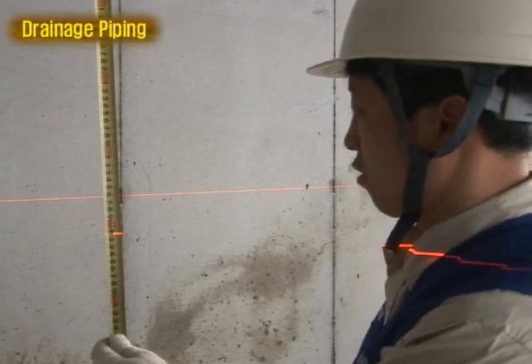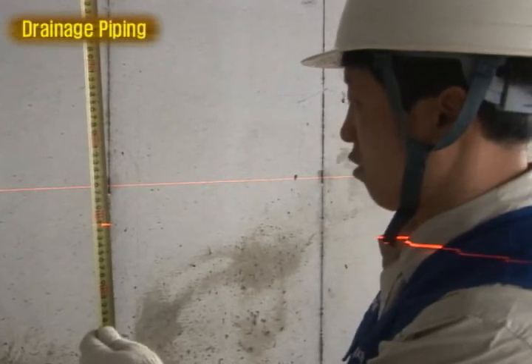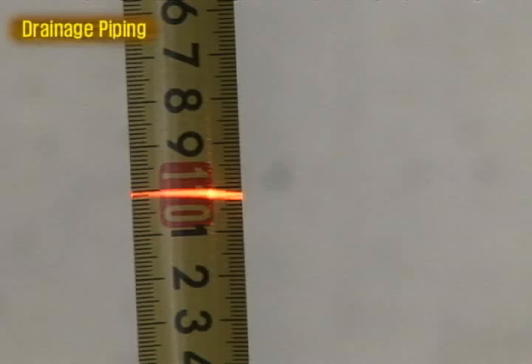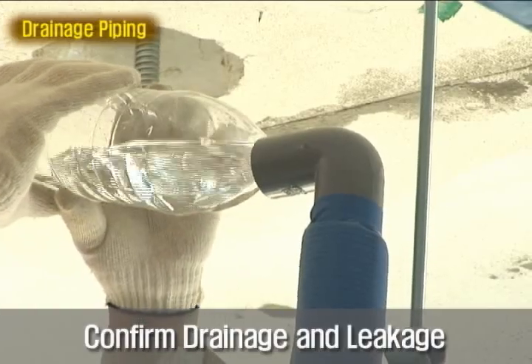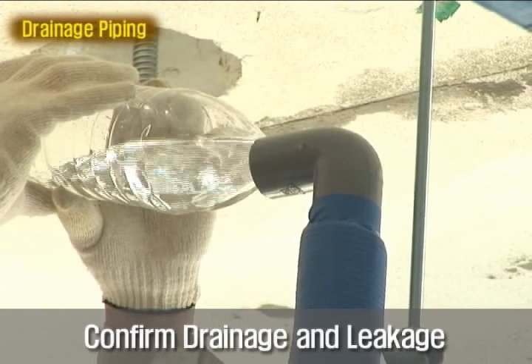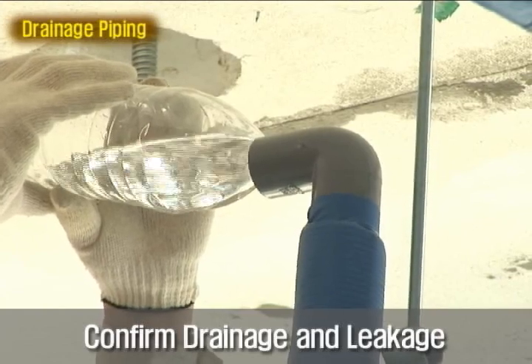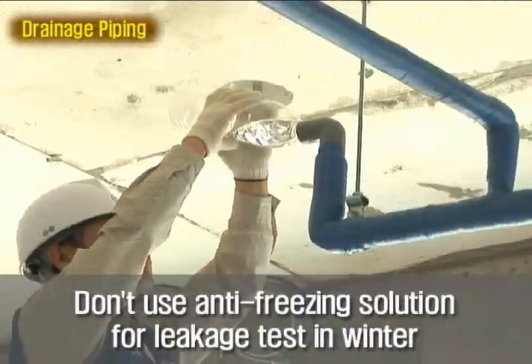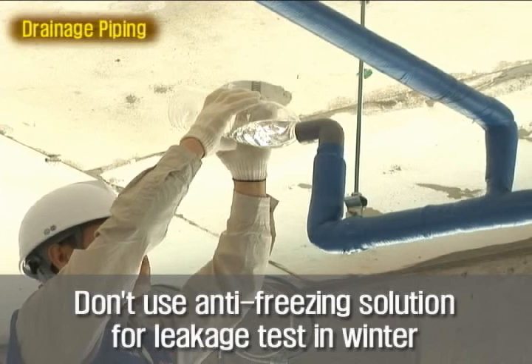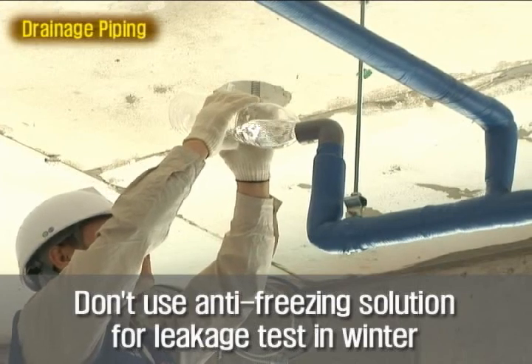If the ceiling is not leveled, laser leveler will be convenient and helpful. After the drain line installation, confirm drainage and leakage by pouring some water into the line. Don't use anti-freezing solution for leakage test in winter.